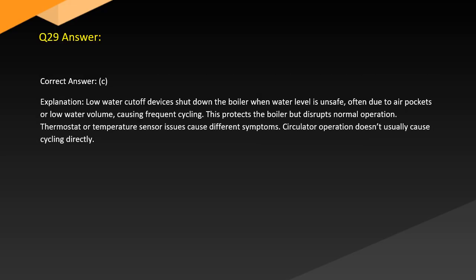Answer. Correct answer: C. Explanation. Low water cutoff devices shut down the boiler when water level is unsafe, often due to air pockets or low water volume, causing frequent cycling. This protects the boiler but disrupts normal operation. Thermostat or temperature sensor issues cause different symptoms. Circulator operation doesn't usually cause cycling directly.